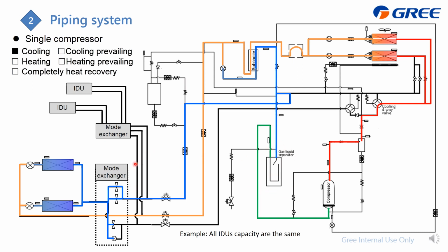As for this part, which is this one, this is the high pressure, where we will always offer the high pressure or hot gas on this pipe. And also just pay attention here at this mode exchanger, as for this branch there is no heating requirement, so these two we make fully closed. As for the other one, we just conduct or offer the low pressure and the liquid and also the high pressure to this mode exchanger. And as there's no valve to connect on the piping of the indoor unit, this liquid still gets through directly to the indoor unit.